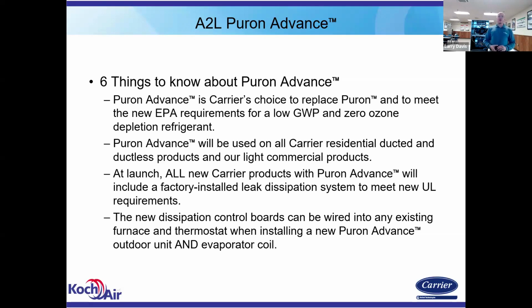All new Carrier products with Puron Advance will include a factory installed leak dissipation that should say all indoor coils, whether it's a fan coil or an evaporator coil. That meets the UL requirements. The outdoor units, that's not on here. The outdoor units, the cabling to the compressor, the contactor, and so forth are designed to meet the UL requirements to mitigate the spark source. New dissipation control boards can be wired to any existing furnace. So you can put our 454B evaporator and condensing unit on anybody's furnace as long as it's a non-communicating furnace.